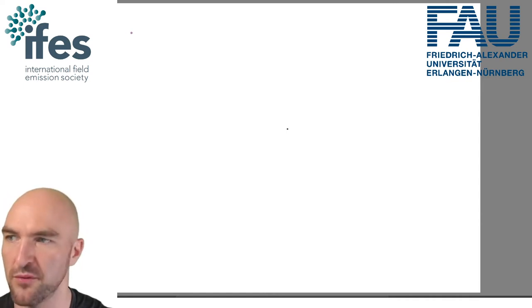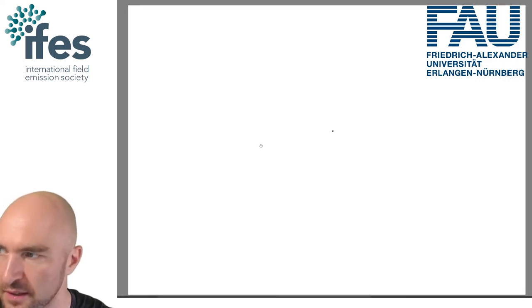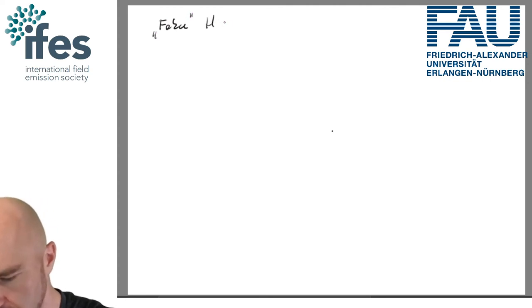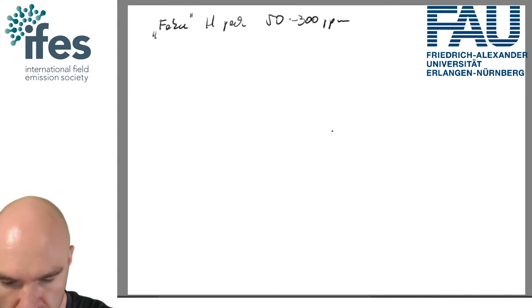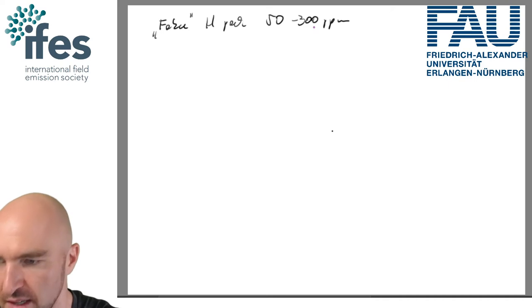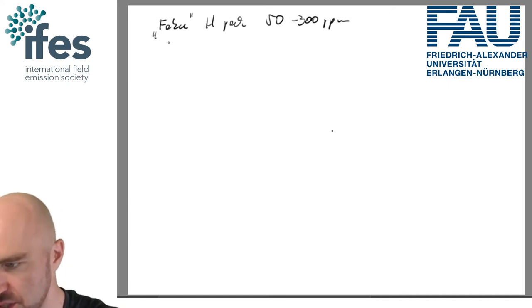So if you've done atom probe before, so if you're not 100% new to atom probe, you might have noticed that there is a fake, let's call it fake because it doesn't come from the sample, a hydrogen peak, which is typically about 50 to 300 ppm. This is obviously not something solid, but something that I've found from looking at a couple of atom probe data sets.